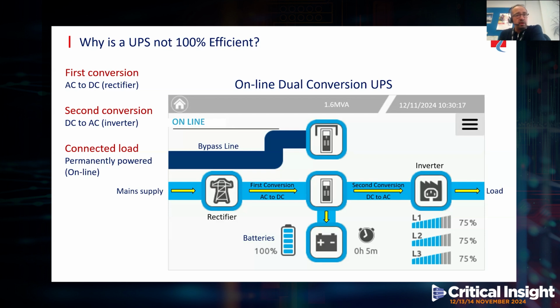But most importantly for the data center's resilience, the online dual conversion UPS is probably the most reliable source of power for the critical loads, especially when used in the various parallel redundant formats and so on. Now, the key requirement for any UPS system is to provide the highest levels of efficiency without compromising on reliability. But don't be fooled, as some manufacturers do juggle these figures a little bit in order to exaggerate the final numbers. And so one thing that we always ask people to do is always check that the data being provided is factual and that it meets the needs of your specific application.